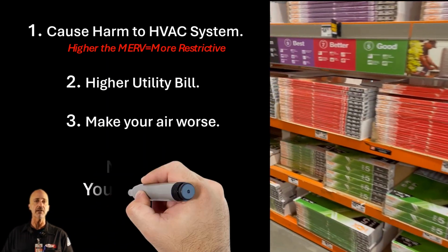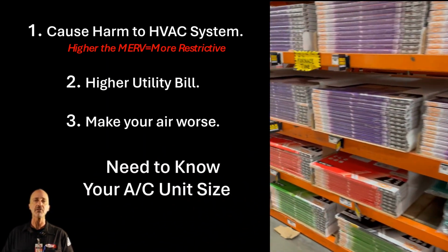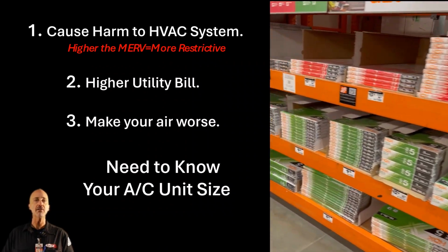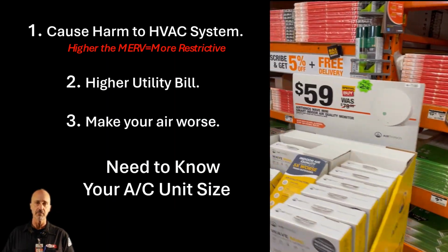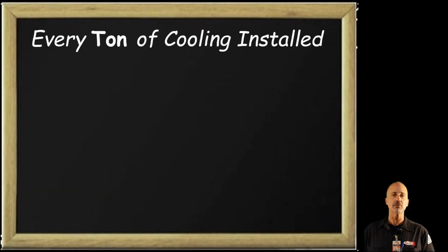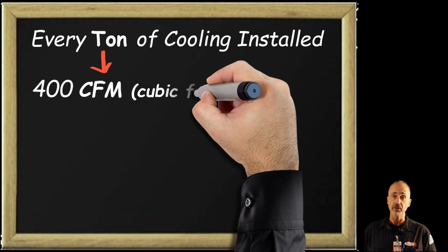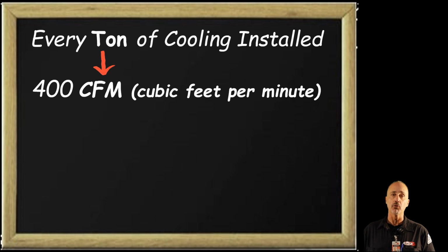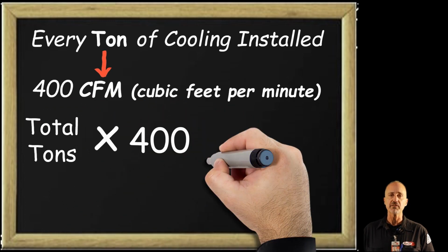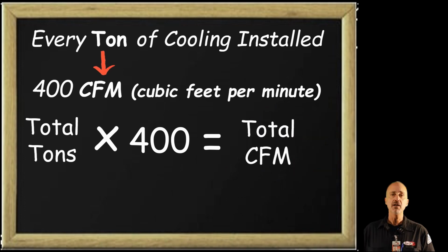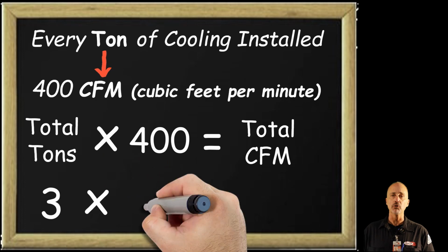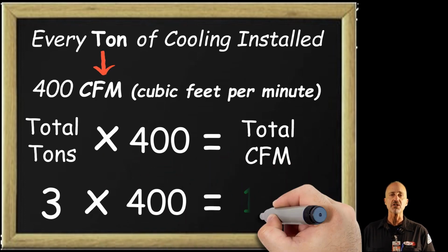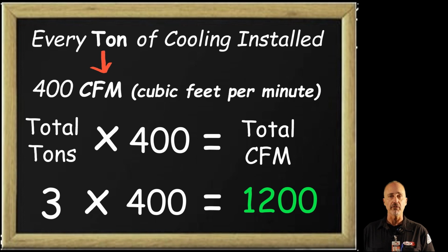You need to know the size of your air conditioning system. If you know how many tons of cooling is installed in your home, then and only then can we start to size the filter correctly. For every ton of cooling installed in your home, we need to supply through your filter 400 cubic feet of air per minute, or 400 CFM. You simply need to multiply the total tons of cooling times 400 to get how many total CFM flow through your filter in order to not have a problem with your HVAC equipment. For instance, if you know you have a 3-ton unit, you would simply multiply 3 times 400, and the total CFM through the filter needs to be 1200 CFM.